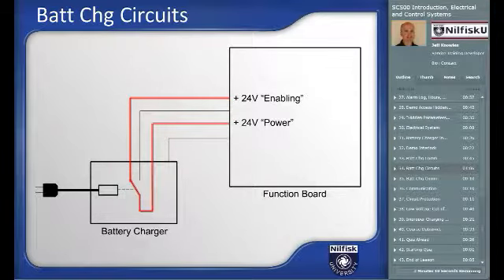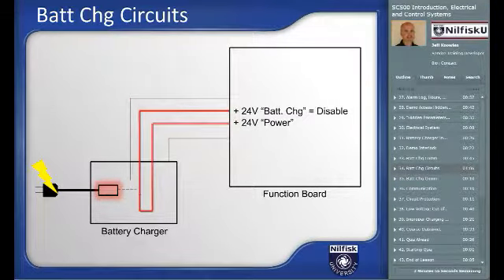When the battery charger is plugged into a power supply, an internal relay is energized, and power is removed from one circuit and applied to another pin on the function board. This circuit is called power supply from battery charger on the wiring diagram. When the function board sees power on this pin, it recognizes that it should be in the battery charging mode, and it disables all machine function, including the drive system. The control panel multifunction display will show the current battery charging phase.